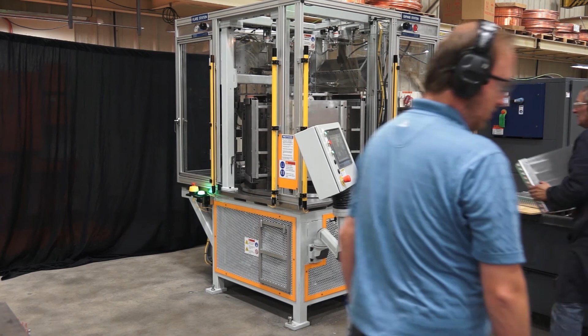There are many innovations in this machine that will make everybody that has this machine in their factory thankful that they have it. We have the ability to give you consistent expansion diameters with the pressure expansion process. We have the ability to give consistent bell depths as well as flare diameters independently. In doing this, we even have built into the process the ability to do tooling changes faster. We have the ability to have a failed coil easily removed from the machine and the machine put back in operation within just a few minutes.